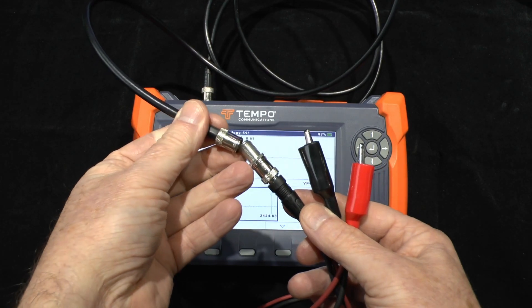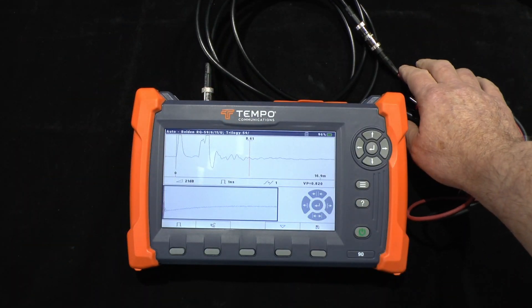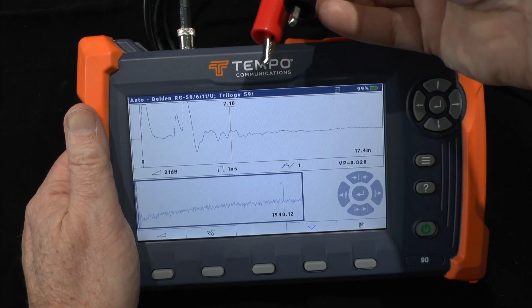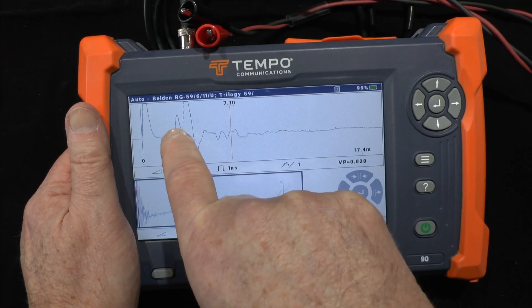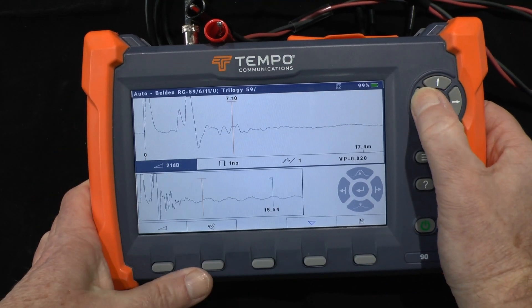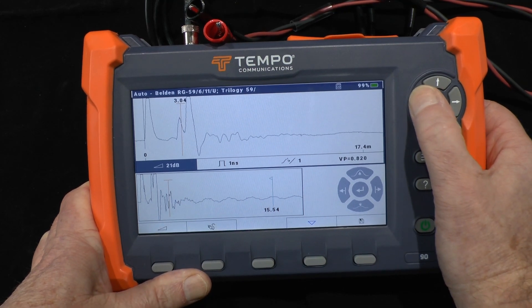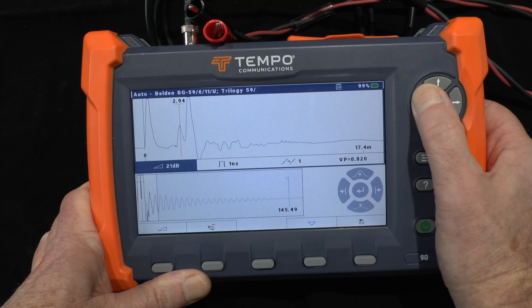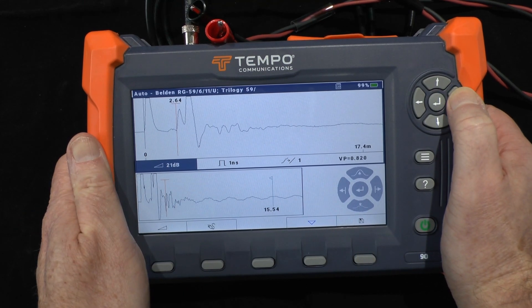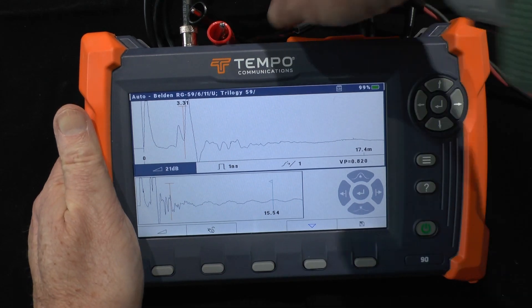As soon as I take the twisted pair adapter and connect it, you can then see that there's now an open circuit a little bit further along. But if I change to the upper trace, we've still got the transition of impedance at the end of the cable here, and then we've got another transition a little further along.